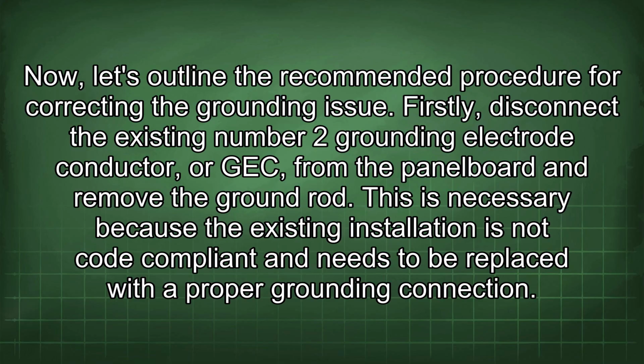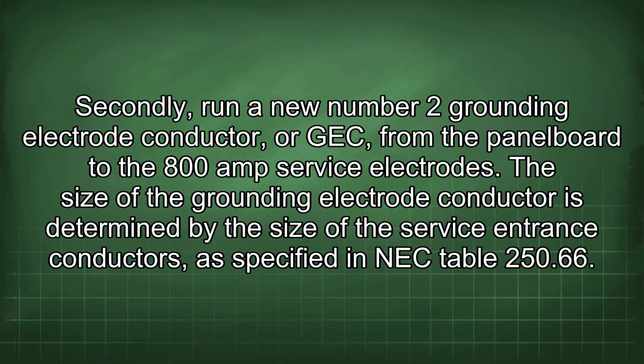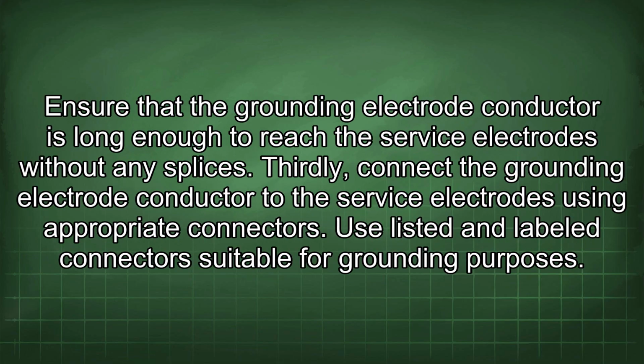Firstly, disconnect the existing number 2 grounding electrode conductor, or GEC, from the panel board and remove the ground rod. This is necessary because the existing installation is not code compliant and needs to be replaced with a proper grounding connection. Secondly, run a new number 2 grounding electrode conductor, or GEC, from the panel board to the 800 amp service electrodes. The size of the grounding electrode conductor is determined by the size of the service entrance conductors, as specified in NEC Table 250.66. Ensure that the grounding electrode conductor is long enough to reach the service electrodes without any splices.